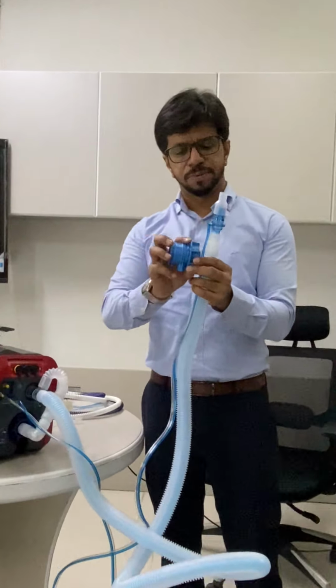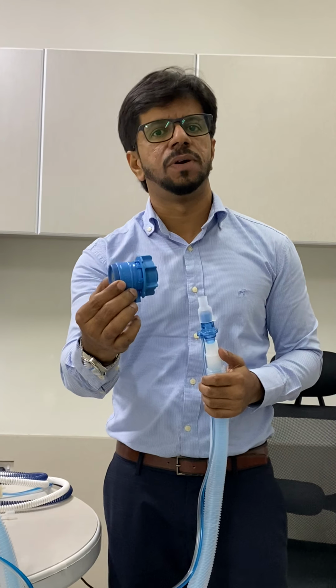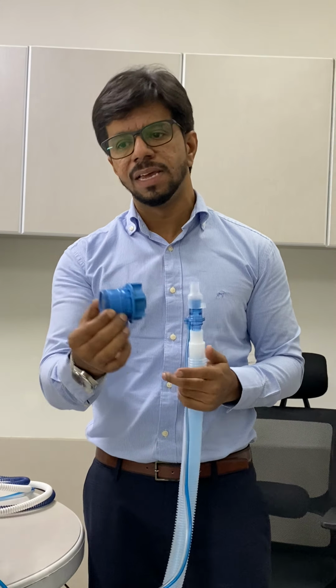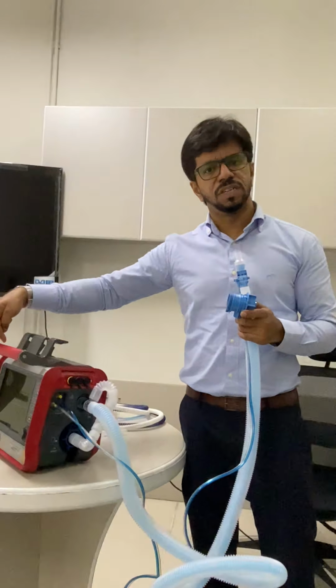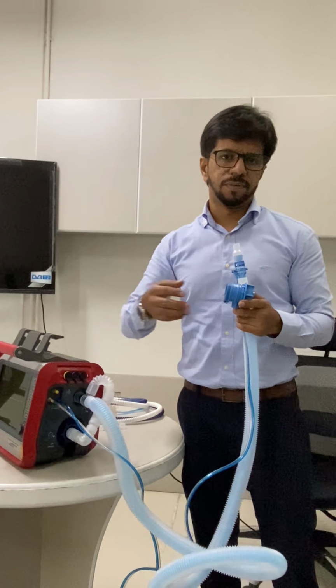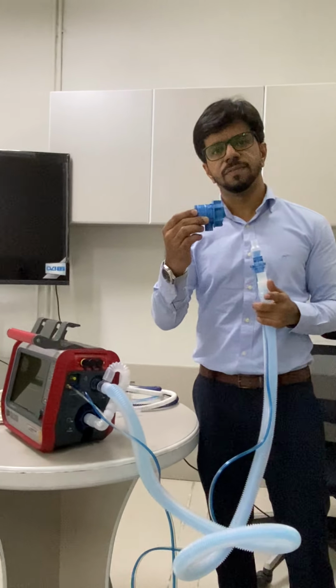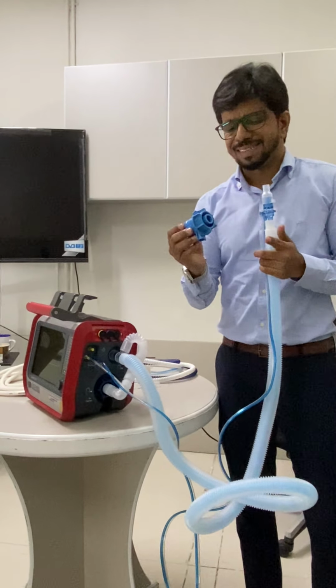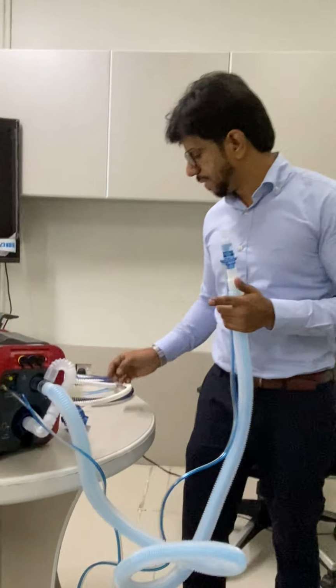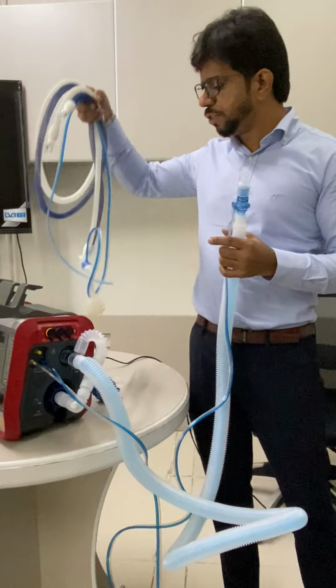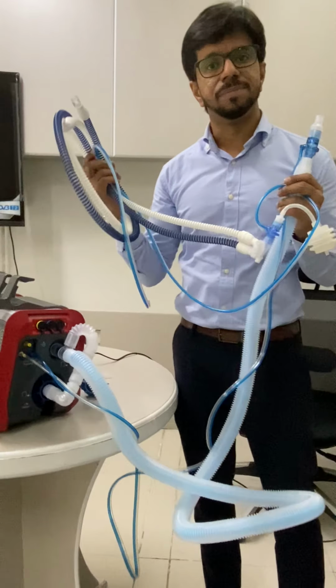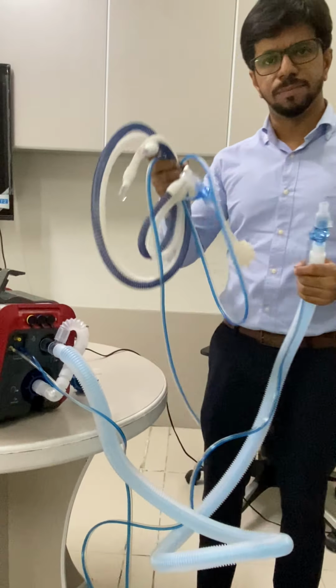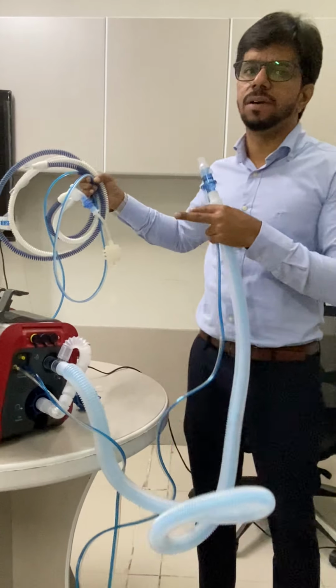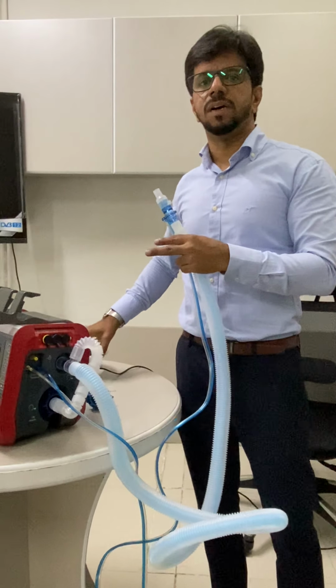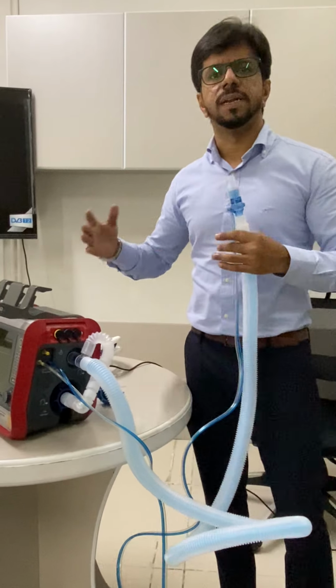If you are choosing the neonatal patient group, you need to change the expiratory valve adapter to the other color coded one, the light blue reusable one. The machine will tell you if you have chosen the neonatal group with the wrong expiratory valve, so you have to choose the appropriate expiratory valve. It resembles the same, but it is only color coded. You will be using a smaller tubing and a smaller flow sensor. But the method is the same. The connection is the same, only the size changes. The machine will automatically detect if you connect the neonatal flow sensor and adapter.